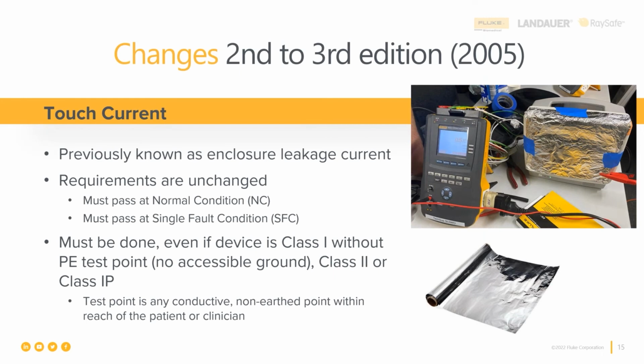Now, there are some changes that I want to highlight here from the second edition of IEC 60601-1 to the third edition. And the third edition was originally published in 2005, believe it or not. But we still all are a little confused or maybe using the older second edition. So there are some things that you need to understand. In the third edition, they changed the name of what we used to call enclosure leakage or chassis leakage current testing to the name touch current.